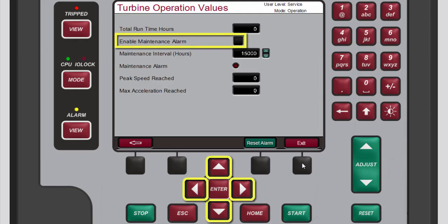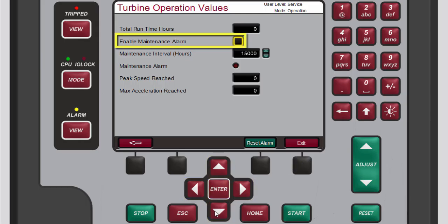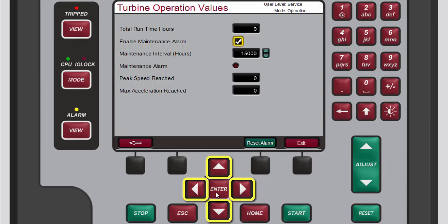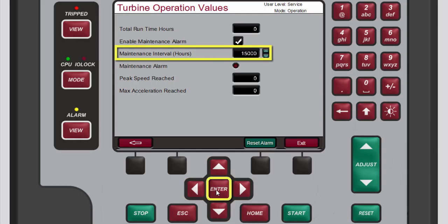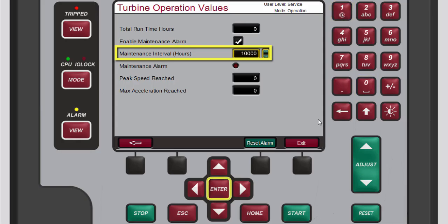To set the maintenance alarm, use the navigation cross keys to highlight the 'Enable Maintenance Alarm' checkbox and press Enter to add a checkmark to the box. Then use the navigation cross keys to highlight the 'Maintenance Interval Hours' box and press Enter to select the current value. Use the numeric keypad to enter the desired number of runtime hours for the maintenance alarm, then press Enter to complete the entry.